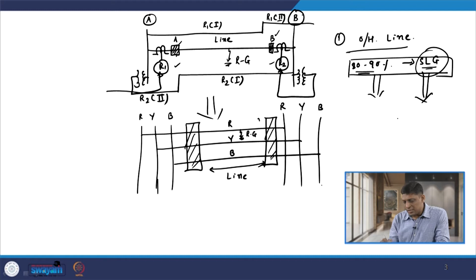Now, this is because in our country we are utilizing gang operated circuit breakers. So, it is known as gang operated circuit breakers. The gang operated circuit breaker means all the 3 poles of the breaker become open simultaneously irrespective of the type of fault. Now, this is against the requirement, because if an R-G fault occurs, then we need to open only the R pole of the breaker.